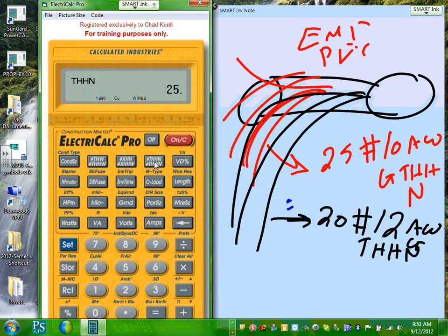Here's a tricky one. Hit that thing again. Make sure you get the actual size of these conductors all together. That will give you the square inch of all these 25 conductors, number 10 all together. Everybody got that one? Now you're done with the 10. Next, you're going to go to the 12. You hit 12 wire size. Now we move to the 12, right? How many of the 12 do we have? I have 20. Hit 20.